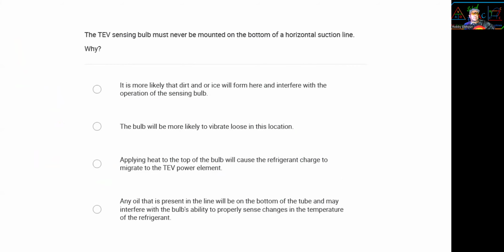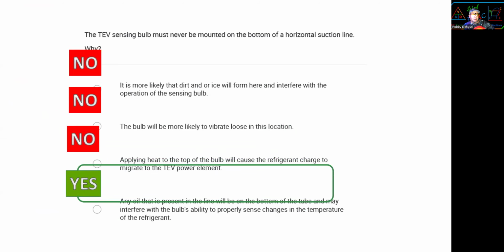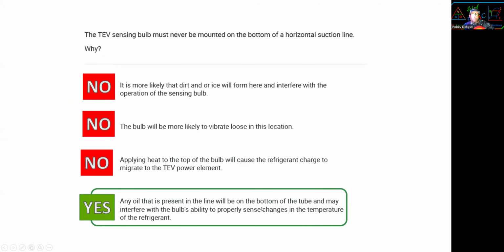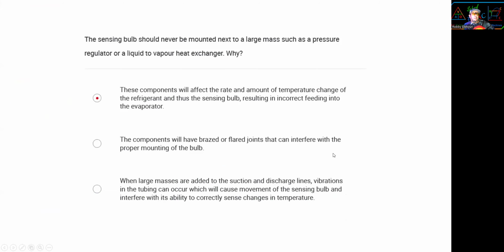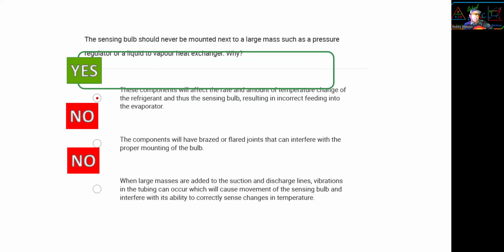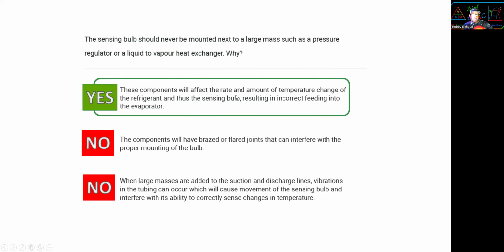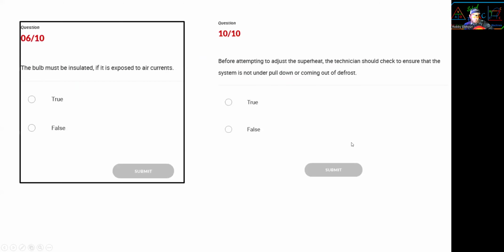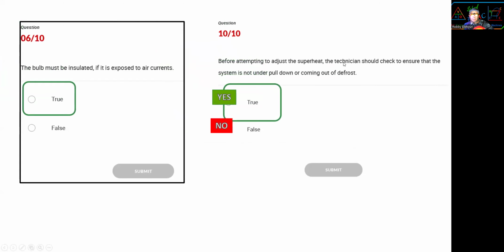The expansion valve sensing bulb must never be mounted on the bottom of a horizontal suction line. Why? We just studied that. Because any oil present in the line will be on the bottom of the tube and may interfere with the bulb's ability. Alrighty, the sensing bulb should never be mounted next to a large mass, because the component will affect the radiating temperature. Right, now, the bulb must be insulated if exposed to air. Yes. And this one, before attempting to adjust superheat, technician should check to ensure the system is not under pulldown or coming out of defrost. Correct.